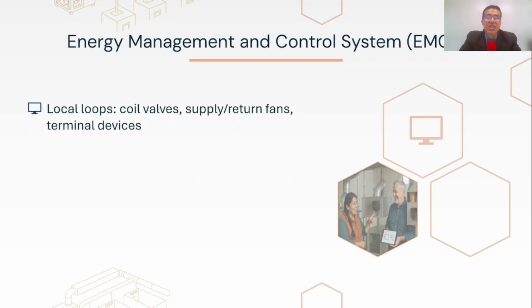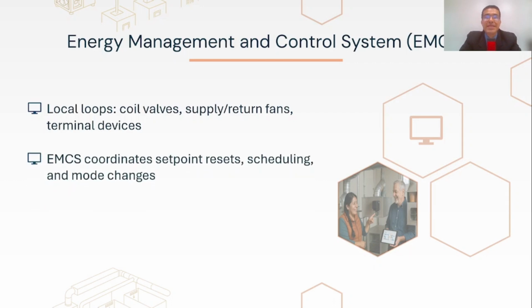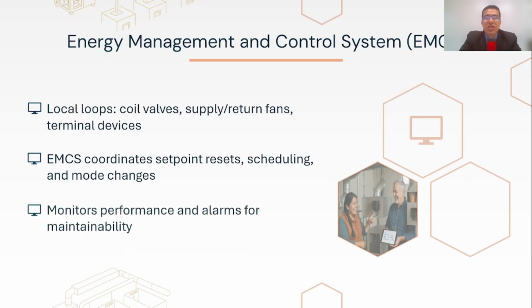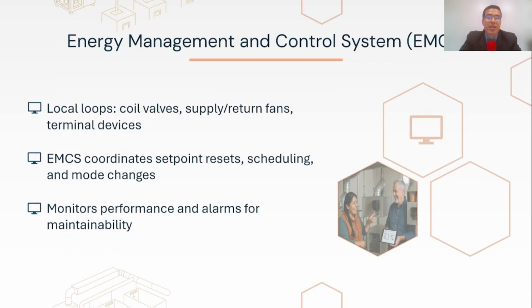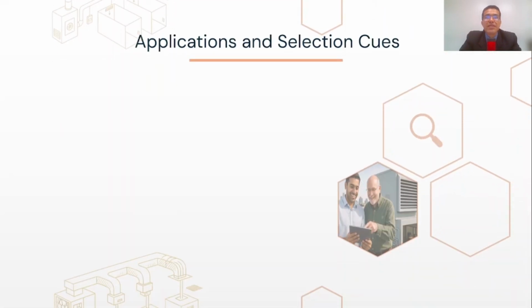So each subsystem includes a local control loop: valves for coils, speed or variable frequency drives, VFDs, for fans, dampers or local fans in terminals. The EMCS supervises the loops with strategies such as supply air or chilled water temperature resets, plant and air handler units scheduling, and economizer enabled where applicable. Supervisory monitoring supports fault response and maintainability while preserving comfort and indoor air quality requirements. Then we have the application.